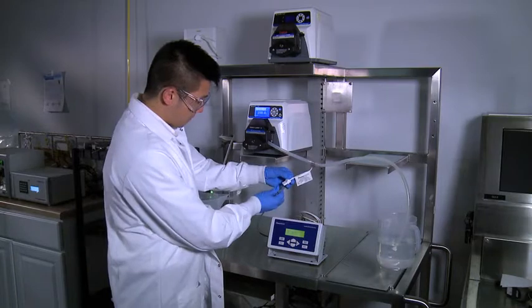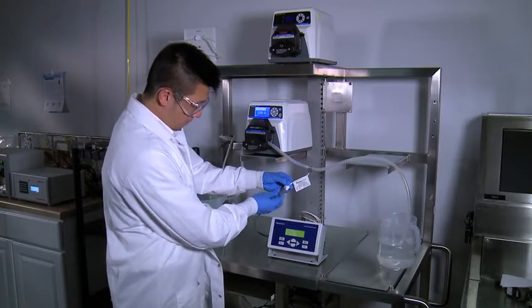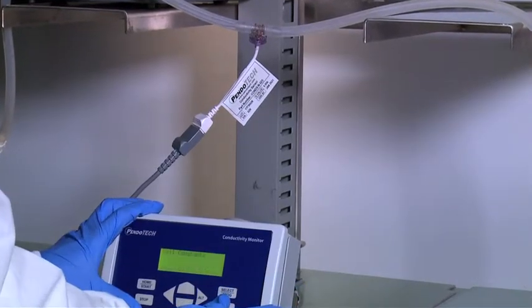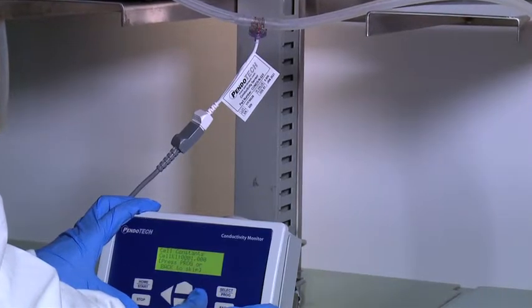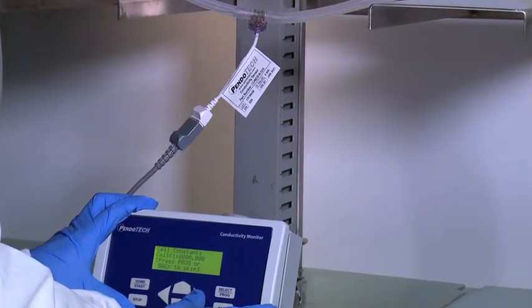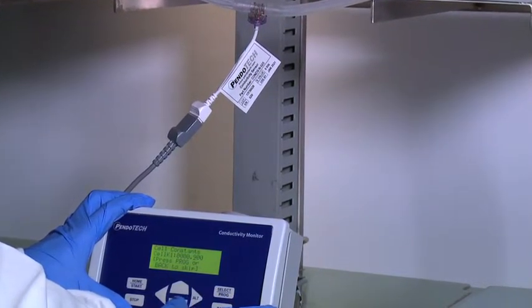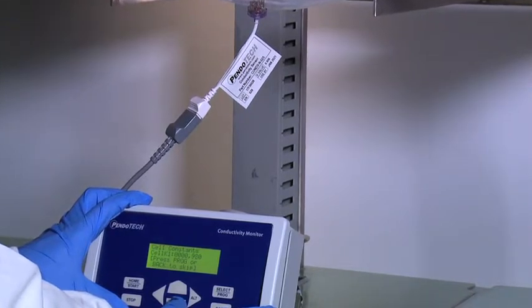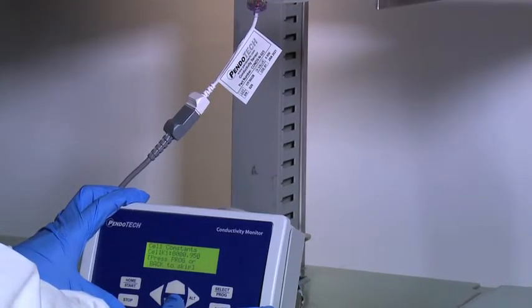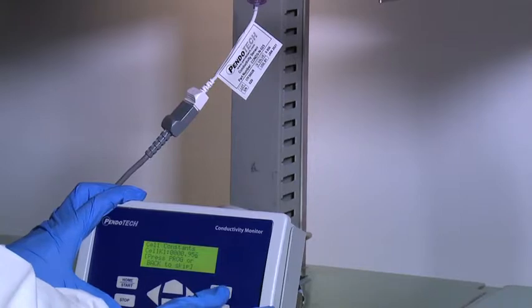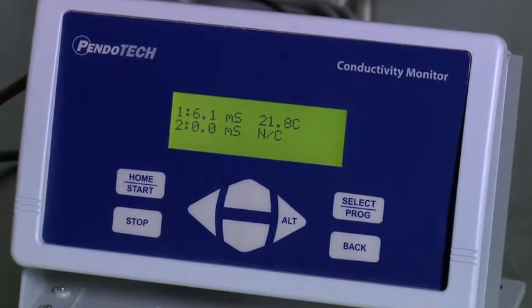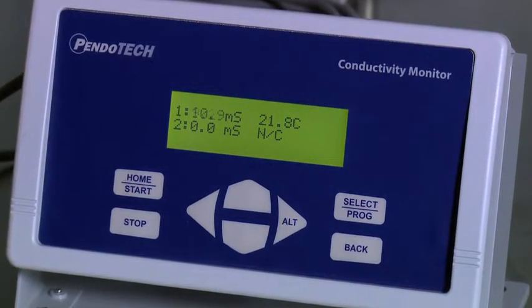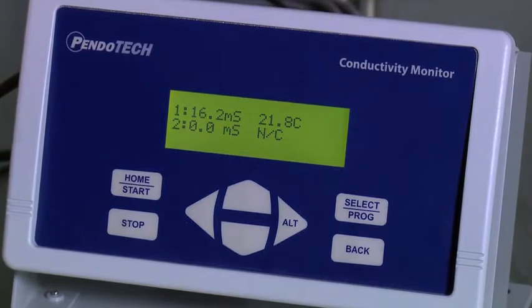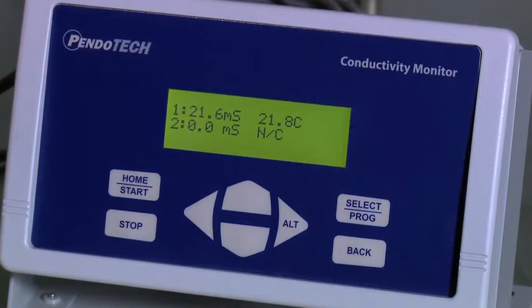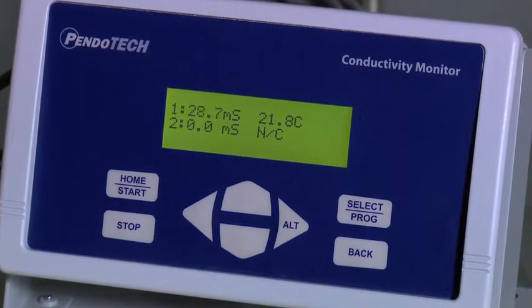When a sensor is connected, the user is prompted by the monitor's display to enter the predetermined cell constant from the sensor tag. This eliminates the necessity in most applications for a user calibration. The K is entered using the monitor keypad. The unit has a fast response time to measuring changes in fluid properties that is important in some applications.